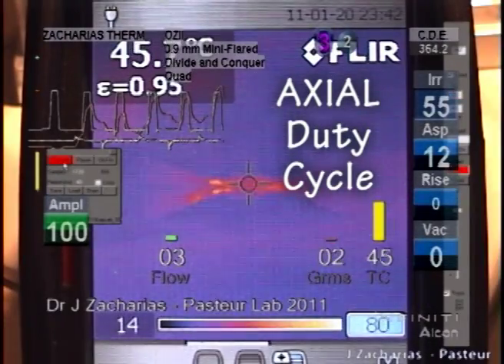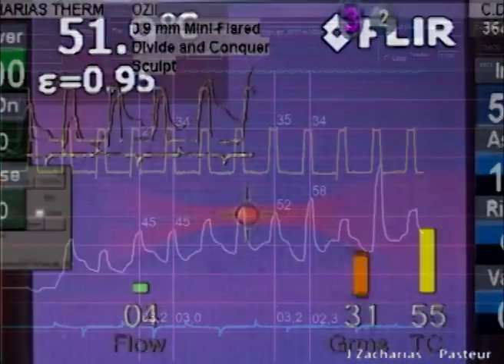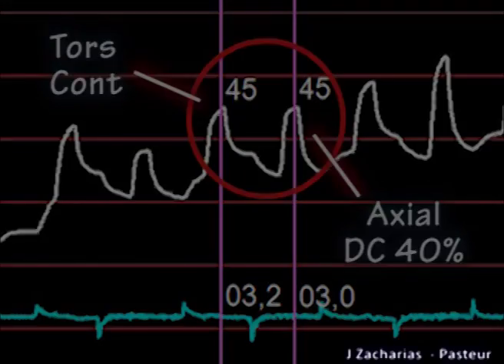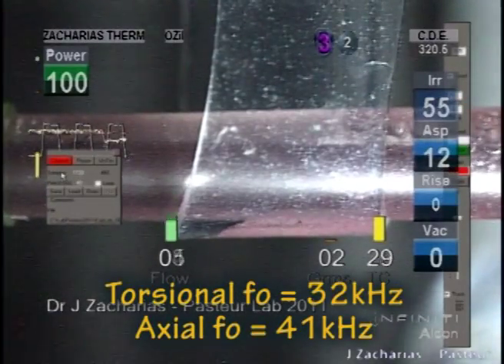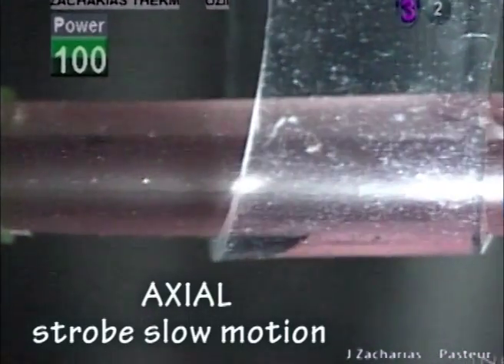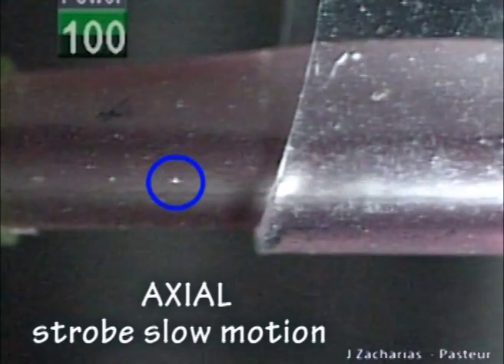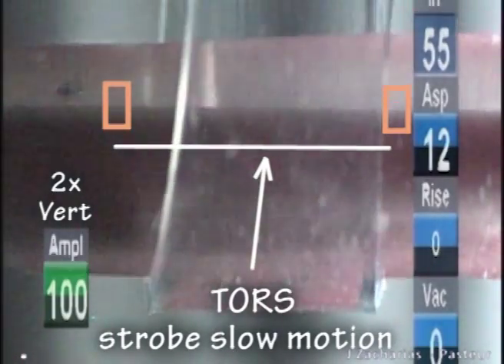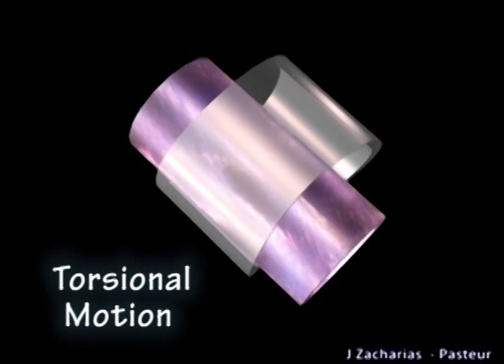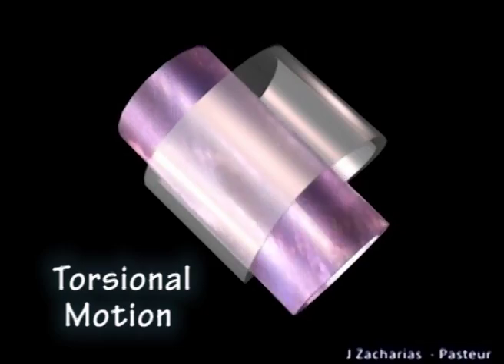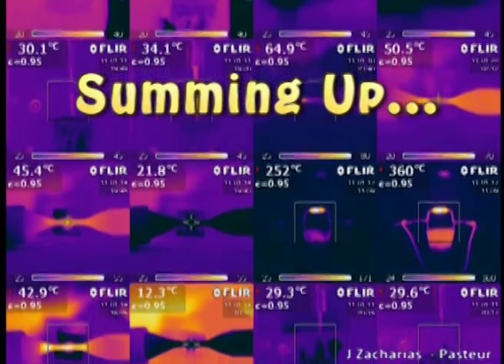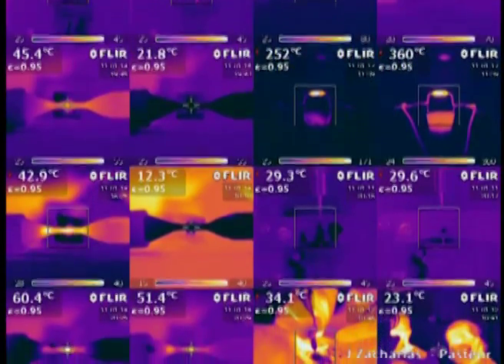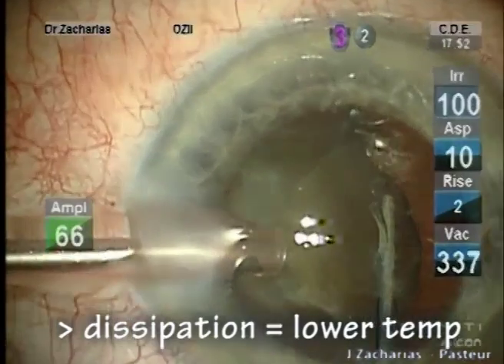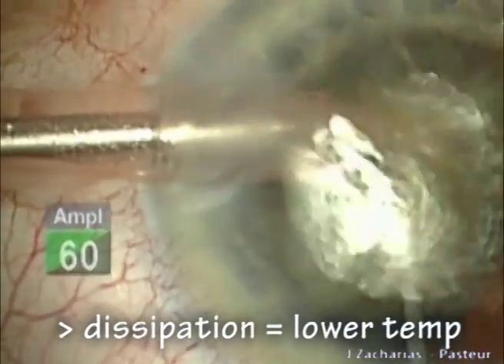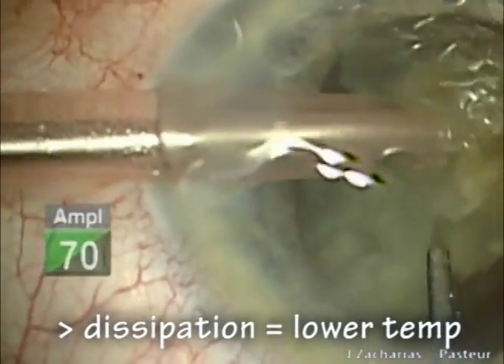Axial power with a duty cycle ranging between 35 and 50% was found to produce temperatures comparable to those of continuous torsional. Besides the lower frequency, to explain these findings, we analyzed probe vibration in the zone of loading. Axial showed a simple back and forth displacement rubbing the sleeve. Torsional showed an undulating movement of the shaft with side-to-side displacements added to rotation. We speculate that the complex nature of the motion pattern with torsional could produce less friction and heat. These experiments were designed to sensibly detect differences in heat generation between torsional and axial phaco terminals. In vivo, dissipation of heat by nerve tissues as well as fluid perfusion will effectively limit temperature to lower levels than those detected in these tests.